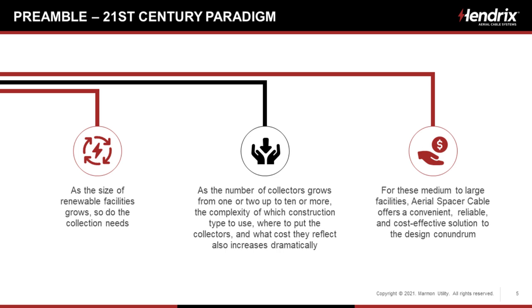As the size of those renewable facilities grows, so do the collection needs. We've gone from 1 to 5 megawatt solar facilities to 500, 600, 700 megawatt facilities. As the complexity of those collection systems grows, the complexity of construction also grows. Where to put the collectors, and what cost they reflect, also increases dramatically. So for these medium to large facilities, and when I say medium to large, I'm talking 100, 150 megawatts and up, aerial spacer cable offers a convenient, reliable, and cost-effective solution to this design scenario.